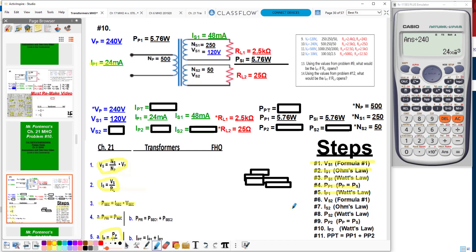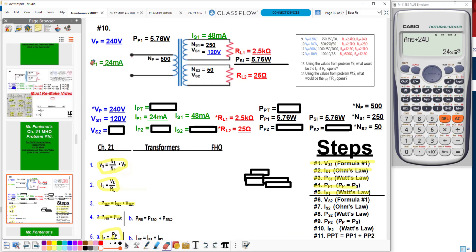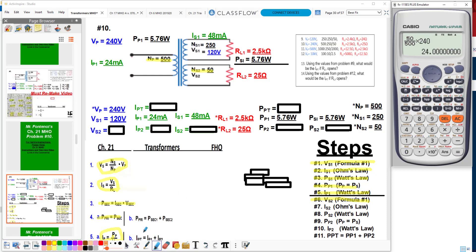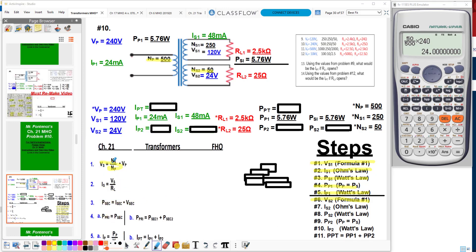Now it's time to find the voltage of the second secondary. I'm going to put a line here because now we're entering into our second set of windings. Step one: I've got to find the voltage of the second secondary. I take the windings — 50 over 500 — times the voltage of the primary, 240. This gives me a secondary voltage in my second secondary of 24 volts.